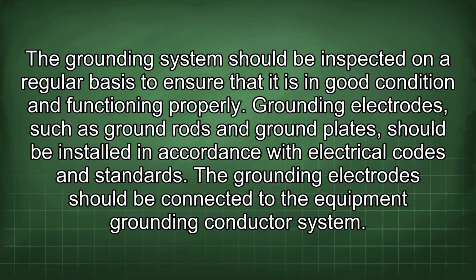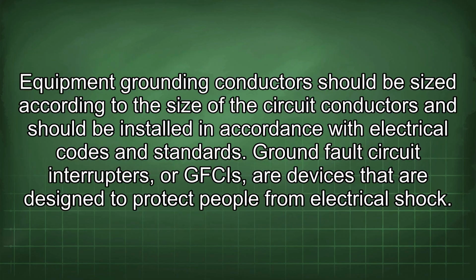The grounding electrodes should be connected to the equipment grounding conductor system. Equipment grounding conductors should be sized according to the size of the circuit conductors and should be installed in accordance with electrical codes and standards.